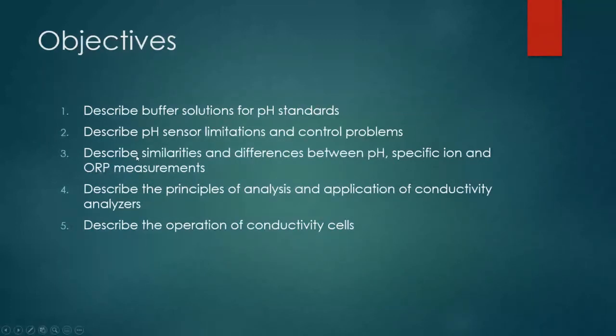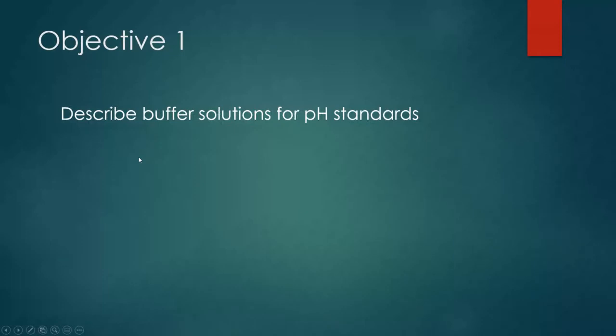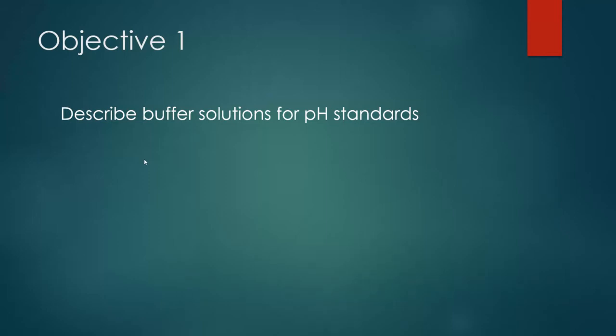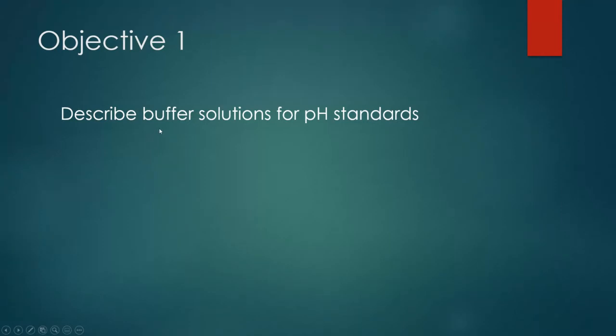Starting with Objective 1, we'll talk about buffer solutions for pH standards. Buffer solutions are the solutions we use to calibrate pH sensors. You can buy them in different pH values, and usually you'll buy them to make bookends on what your measurement value is. So if you're expecting to measure a pH of 7, you'd get one buffer on the low side and one on the high side — maybe a number 4 and a number 10 buffer.